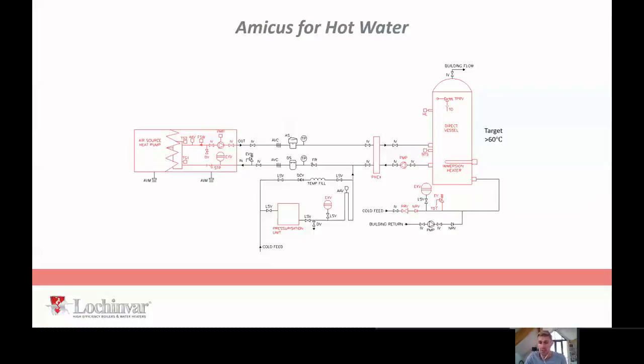So for hot water, any public health engineer in here, I'm sure, will be wanting to see 60 degrees centigrade in their hot water vessel, which will be serving the building. To keep the efficiencies up, our heat pump flows at 63 degrees centigrade. Now, remember, we've got a 5-degree delta T, so we flow at 63, we return at 58. The plate heat exchanger is spec'd to only lose 1 degree across it. So what we end up with is these pretty substantial plate heat exchangers with big surface areas. And what that allows us to do is, even with a 5-degree delta T on the primary, on the secondary side, we flow out at 62. That 62 degrees centigrade will then flood the top 2/3 of this vessel, distribute off to the building at over 60. So our public health engineers are typically happy.